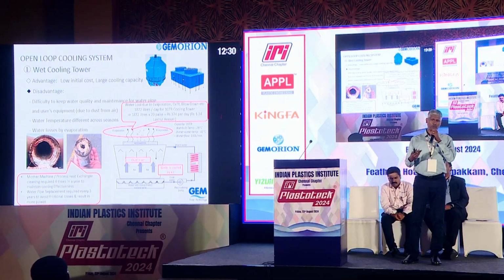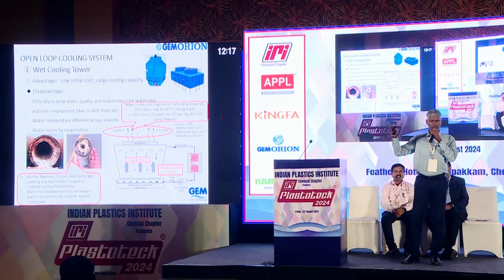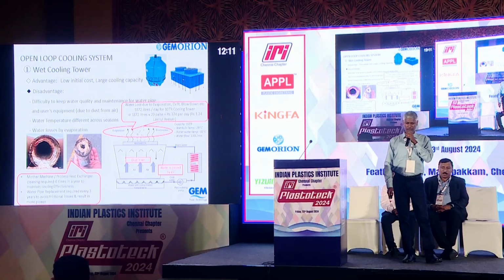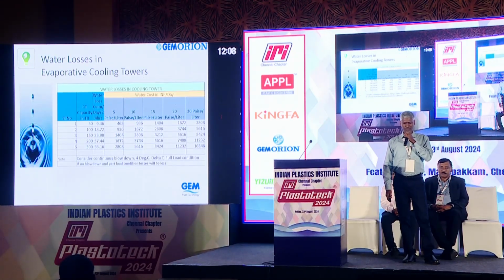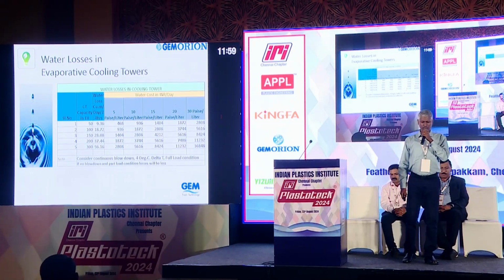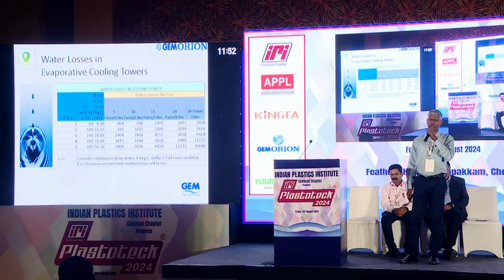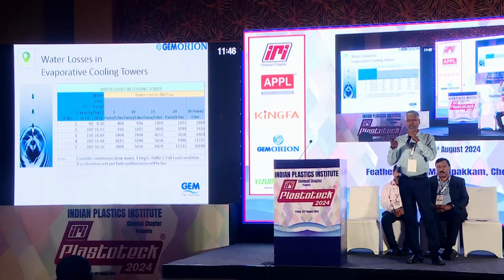That means already for getting that treated water, some amount of water is wasted. So we are wasting water there, and then subsequently in the form of evaporation, a lot of water is getting wasted. So here is a typical data point: for a 100 TR cooling tower, considering water cost as 5 paise per liter, we are spending about 936 rupees for water in a day, close to 1,000 rupees. In a year, around 3.5 lakhs, which we generally don't notice.